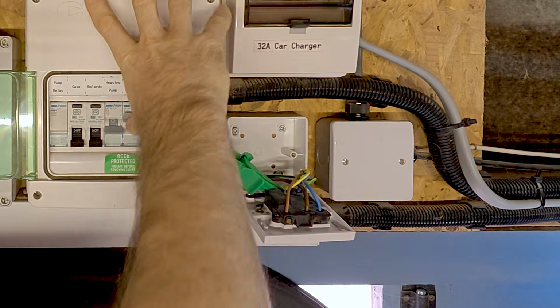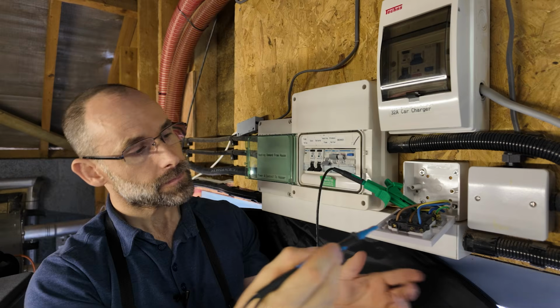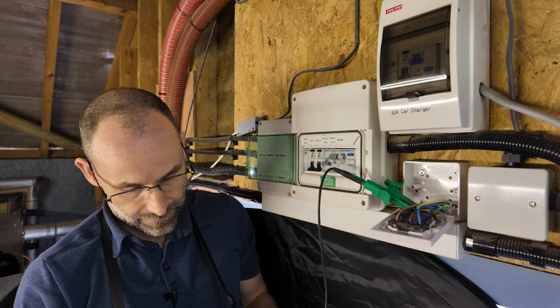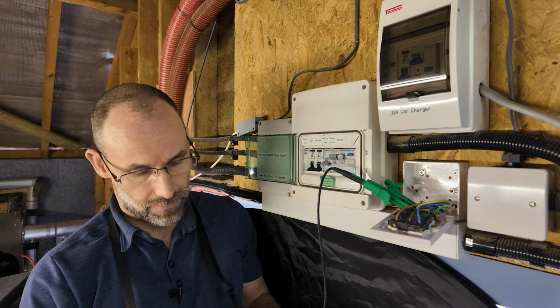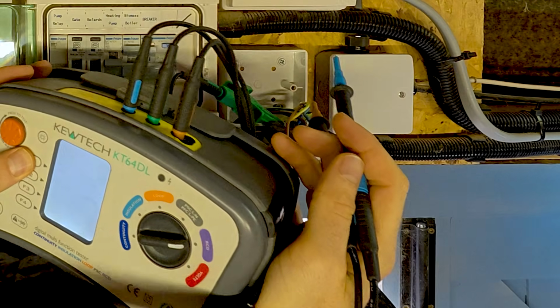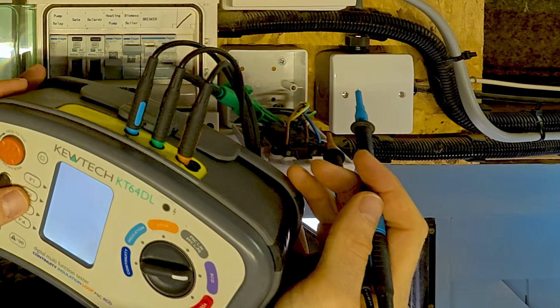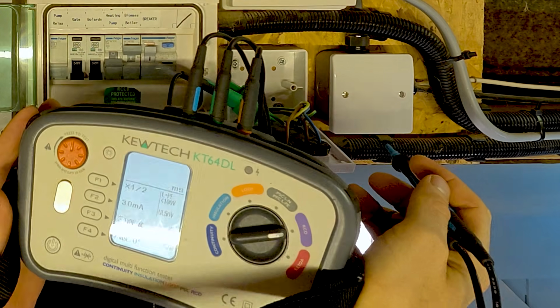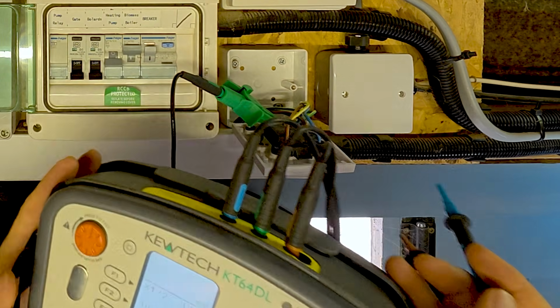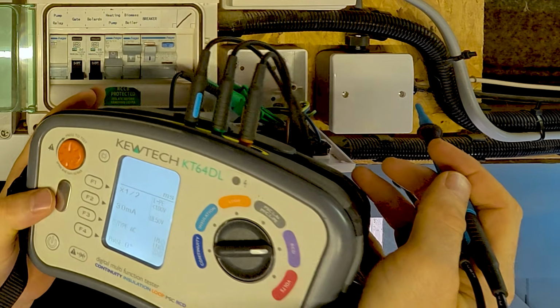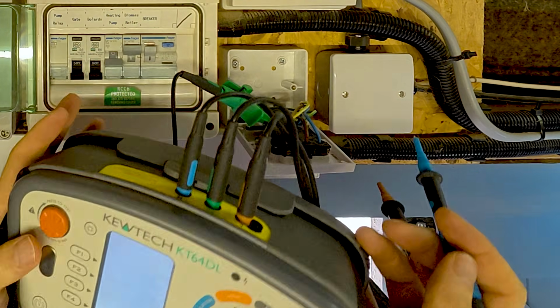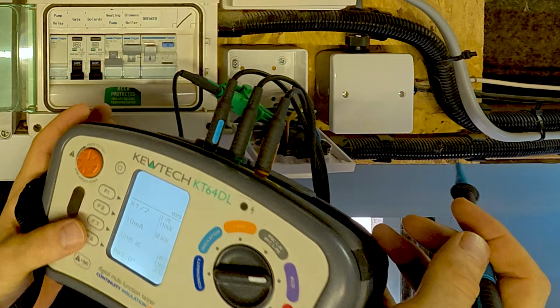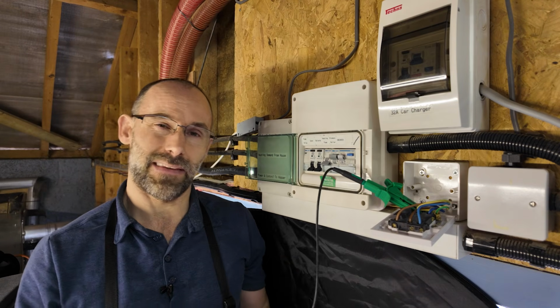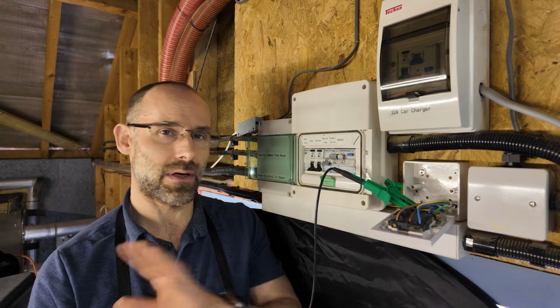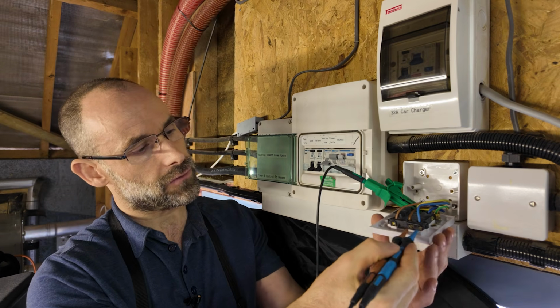So I'm going to turn the RCD and the circuit in question on. Then on my meter, I need to tell it various different things. I need to tell it what test current I want to use, which in this case is 15 milliamps. It's half the current it should be tripping at. I want to tell it that it's a 30 milliamp rated RCD, and that it's type AC. They've got little symbols on them, different types. We also test this at different phases, but for simplicity, I'm going to leave that out. Let's just do the basics.